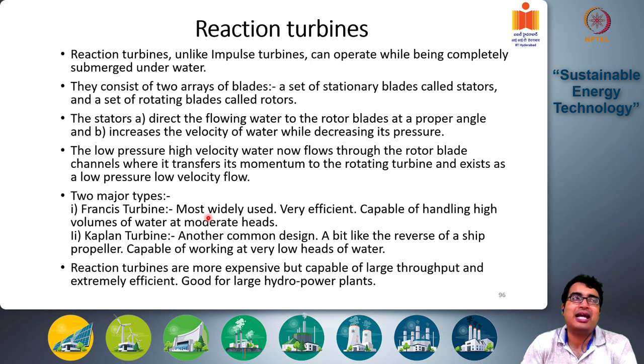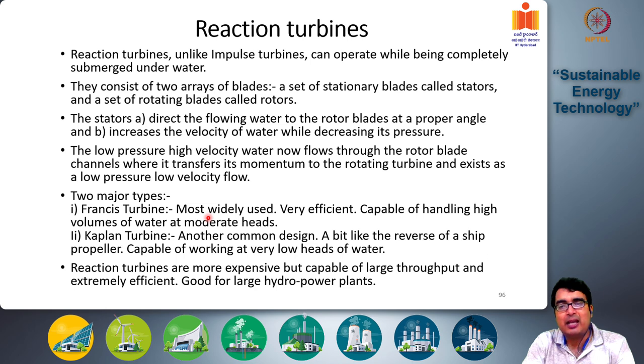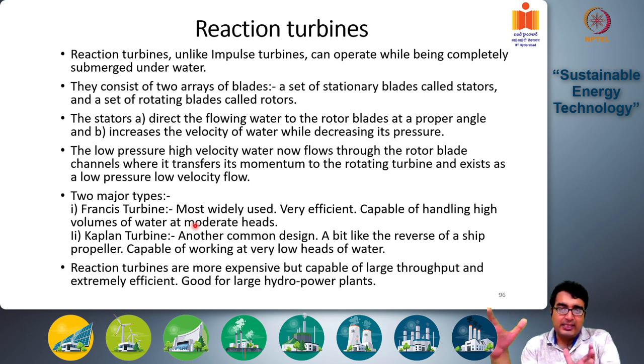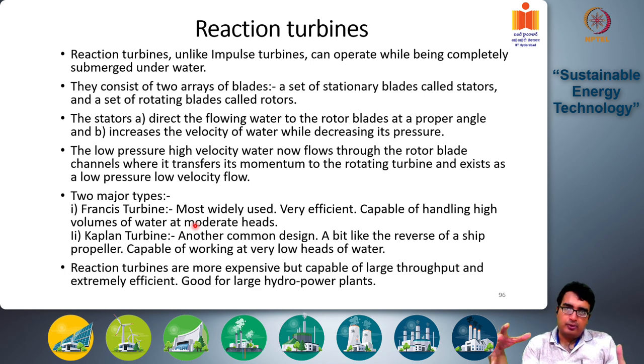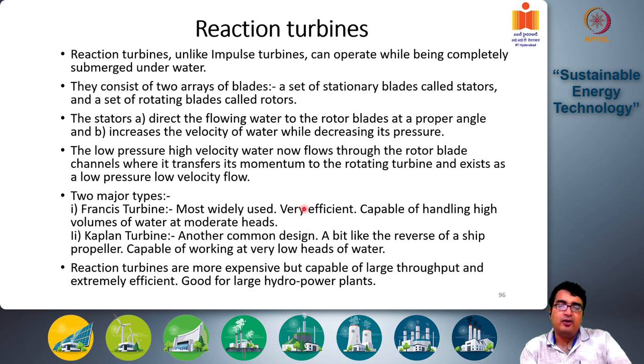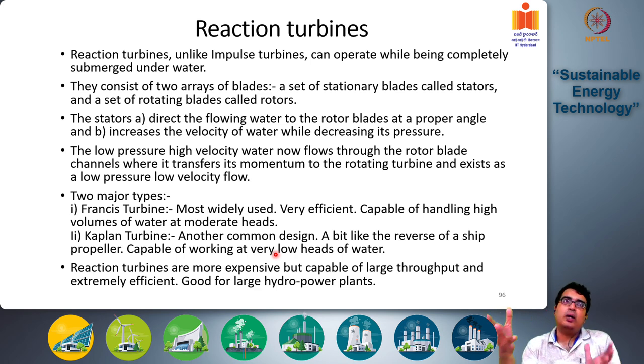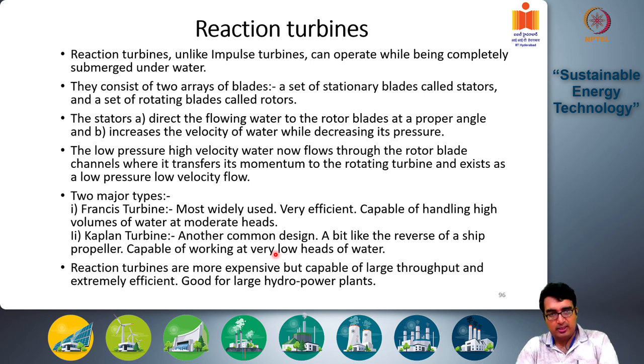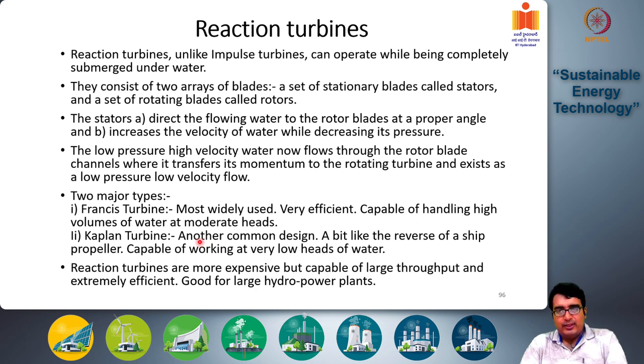The Francis turbine is the most widely used type in large hydropower plants. It is very efficient and capable of handling high volumes of water at moderate heads. One of the advantages of reaction turbines is they can handle large volume flow rates of water, and the Francis turbine specifically can handle very high volume flow rates at relatively moderate heads — even heads lower than what Pelton turbines can handle — at very high efficiency.